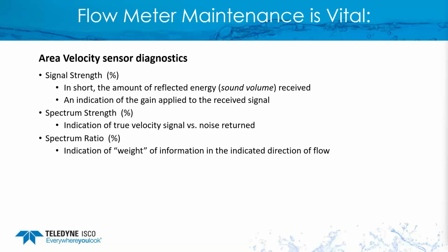Other diagnostics that you may have, like on area velocity sensors, is the signal strength. In short, it's the amount of reflected energy received. Think of it as the gain applied to receive that signal, like a hearing aid. How much do you have to turn that hearing aid up to be able to get a good signal? And so that's our signal strength. What I find more important is the spectrum strength, and it's the indication of the true velocity signal versus return noise. So I've got my hearing aid turned up, and how much of that am I hearing back?